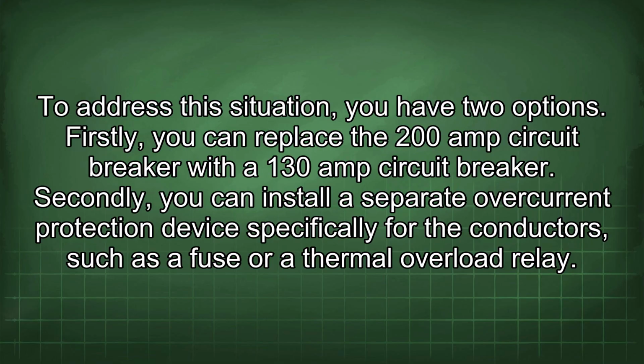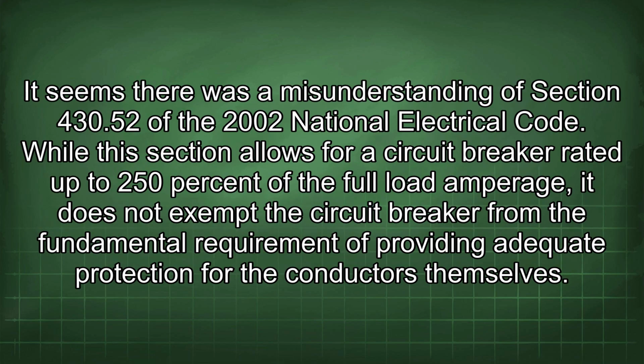Firstly, you can replace the 200 amp circuit breaker with a 130 amp circuit breaker. Secondly, you can install a separate overcurrent protection device specifically for the conductors, such as a fuse or a thermal overload relay. It seems there was a misunderstanding of Section 430.52 of the 2002 National Electrical Code. While this section allows for a circuit breaker rated up to 250% of the full load amperage, it does not exempt the circuit breaker from the fundamental requirement of providing adequate protection for the conductors themselves.